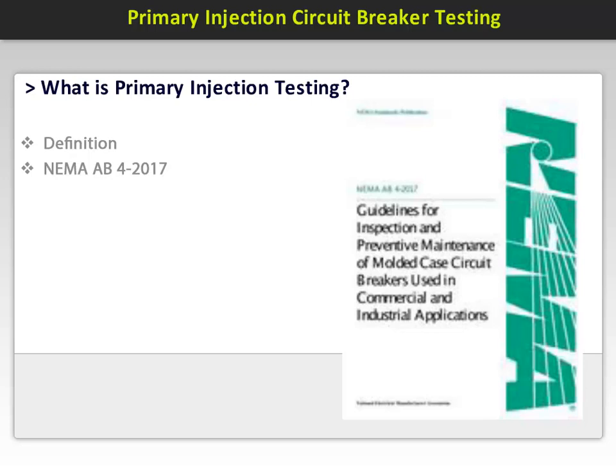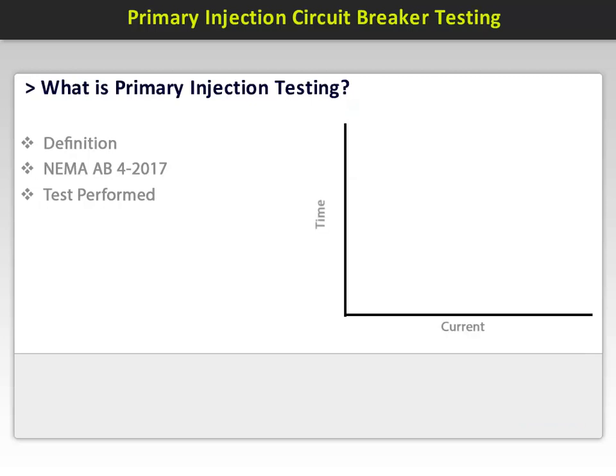There are four tests that need to be performed. Let's look at these tests and illustrate where they exist on a breaker trip curve. First is the long time delay and pickup, represented by the blue line seen here. This provides protection for overload conditions. The test current is injected in each pole and the trip time is recorded.